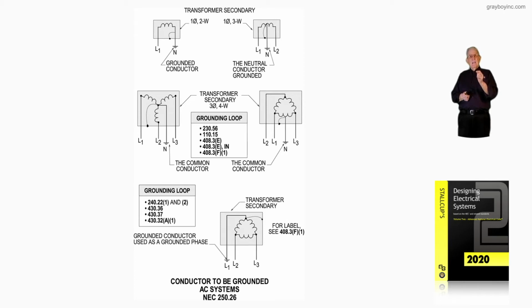Now, the next illustration is a Y to the left. And notice it's a Y system, and you can pull three hots with one neutral. The previous illustration to the right that we just looked at, you could pull two hots with one neutral. But that's it. You couldn't pull three hots with one neutral from the same phase, or two hots with the neutral from the same phase. In other words, you'd have L1, L2 neutral, L1, L2 neutral. That's what I'm trying to say here.